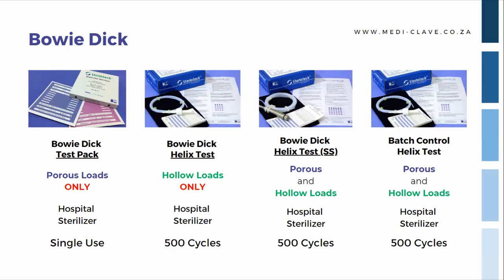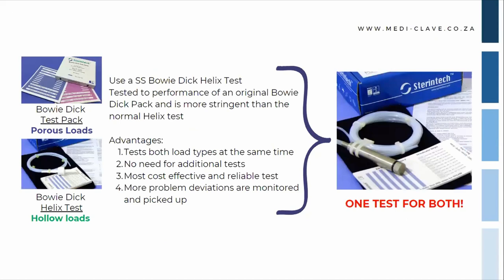However, the problem with this is most CSSDs don't have a set load, they have mixed loads. The second problem is two Bowie Dick test packs at the same time influence each other. And the third problem is if you jump between the Bowie Dick test pack and your Bowie Dick helix test pack, you'll lose a capacity of 20%, which you could have used to maybe sterilize an object. So the stainless steel Bowie Dick helix test is tested to perform like the original Bowie Dick test pack and is more stringent than the normal helix test pack.